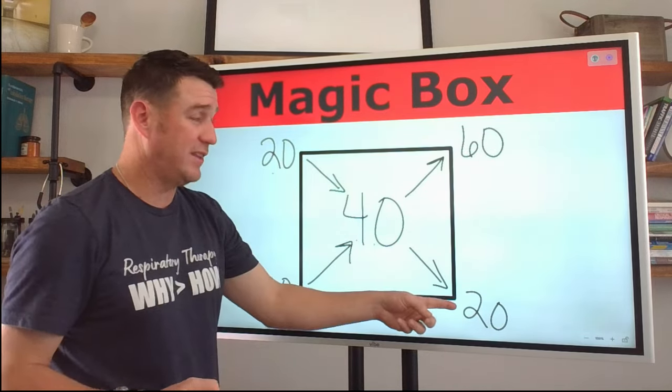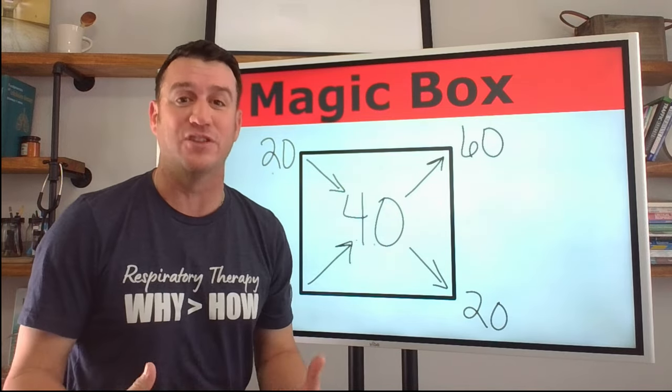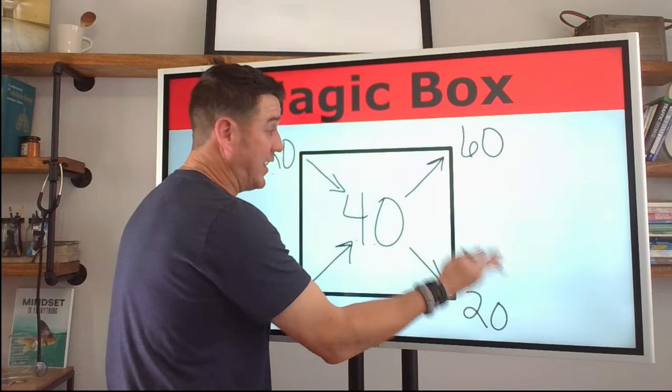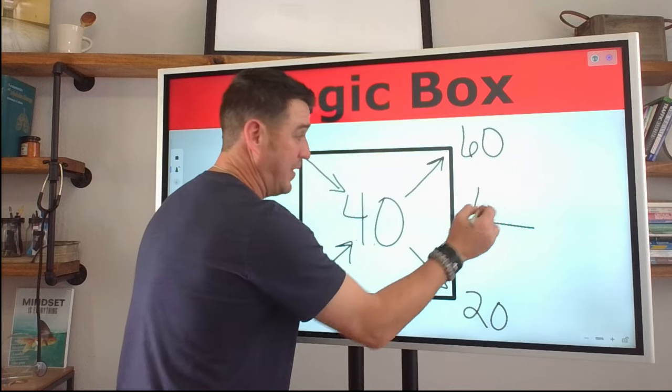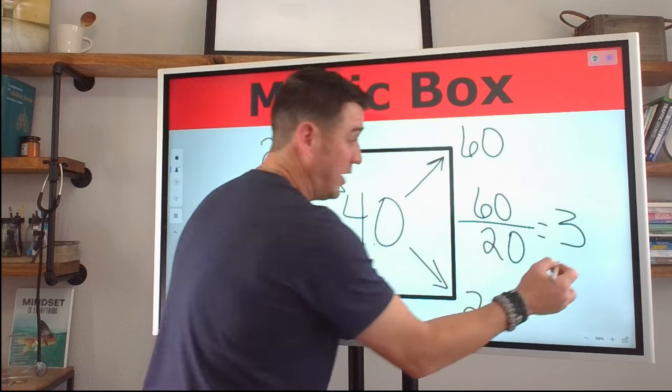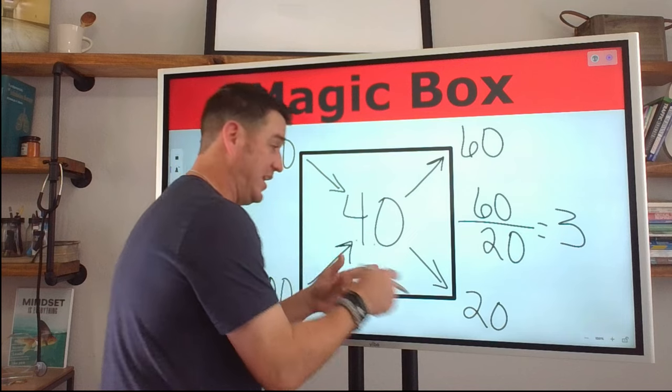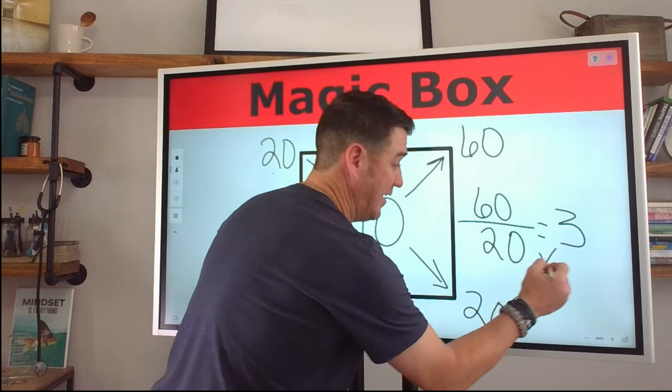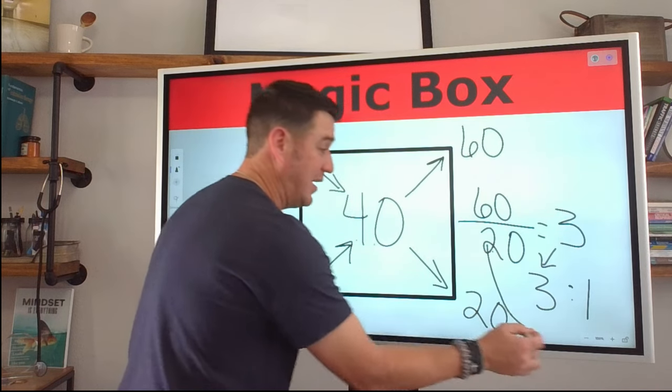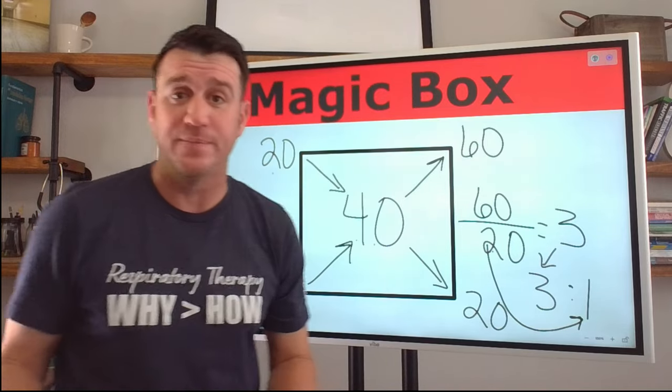Now we do the same thing here, diagonally this way, 100 minus 40 is 60. And here's what we're left with. Now you say, okay, that's not my air to oxygen ratio. It's not, but now we have the numbers we need to divide by. So now they're already in order. So now you just have to divide 60 by 20. So 60 divided by 20 equals three. And your air to oxygen ratio for 40% is three to one.